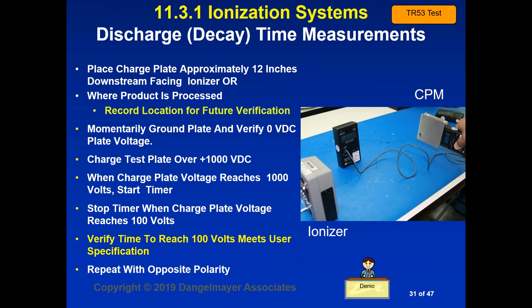You want to momentarily ground the plate of your measuring instrument and verify 0 volts DC on the plate. Then you're going to charge that test plate to over 1,000 volts DC. And then when the charge decays to 1,000 volts, you're going to start your timer. Your timer is going to run until the charge plate voltage reaches 100 volts. So you're making a measurement from 1,000 volts to 100 volts. And you want to verify that the time to reach 100 volts meets the user specification. Might be 10 seconds, might be 20 seconds, might be as much as 60 seconds for some ionizer applications. But whatever your specification is, you're going to make a measurement that verifies that you're in the required measurement range.